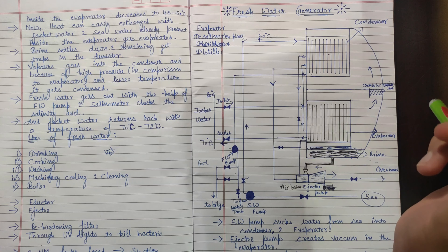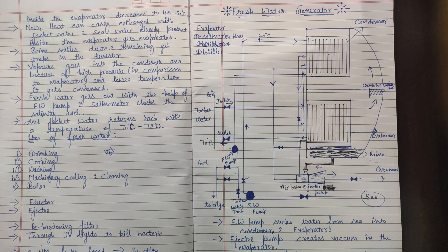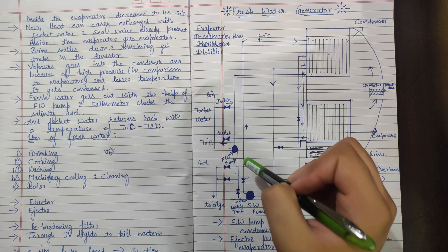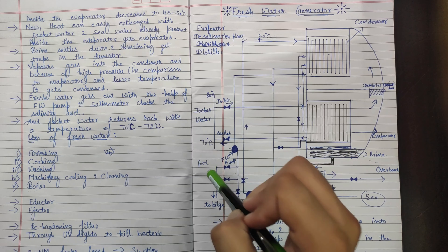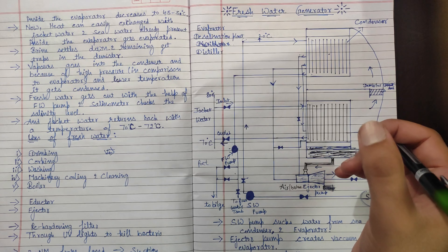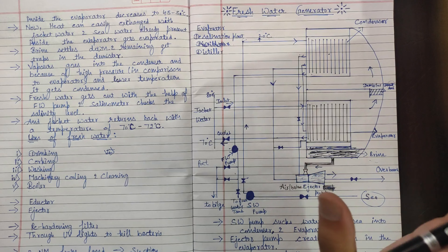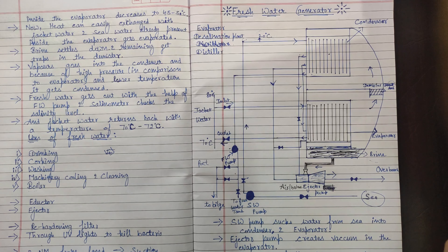When the vapors get condensed, that condensed water is our distillate water — we have reached our end point. We bring out this distillate water through a line using the fresh water pump. There is a meter called the salinometer which checks the salinity level of the water. If the salinity level is not appropriate, it recirculates the water or sends it to the bilges. If the content is acceptable, it sends the water to the fresh water tank.